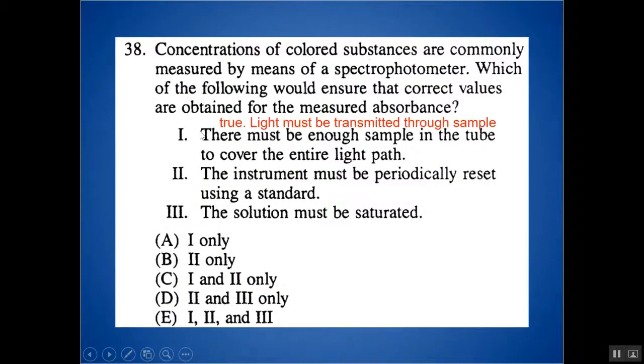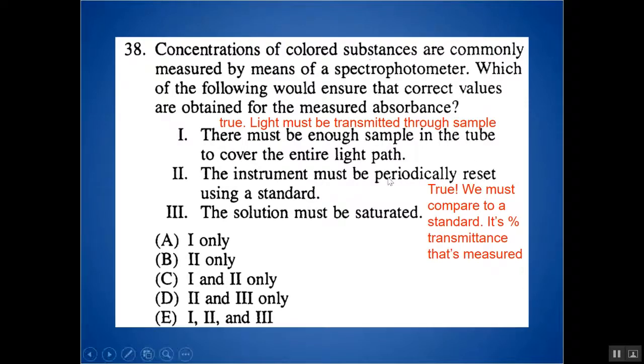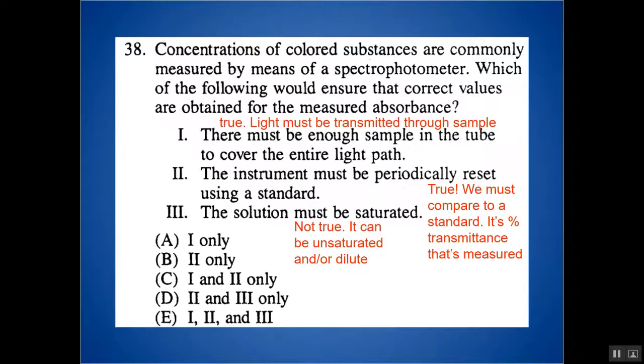In the lab, there must be enough sample in the tube to make sure the entire light path is covered — fill tubes at least three-quarters of the way. If you don't have enough solution, the light might pass through an empty test tube rather than the solution. You also want to periodically calibrate your machine using a standard, as described before. The solutions do not have to be saturated — they can be unsaturated, concentrated, or dilute. You're figuring out the concentration based on the absorbance.